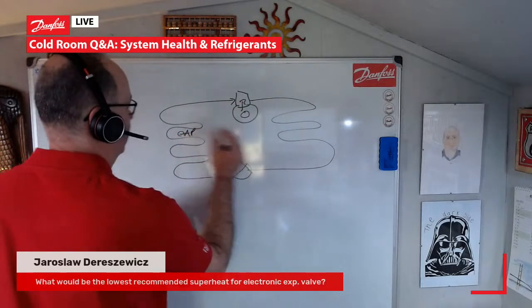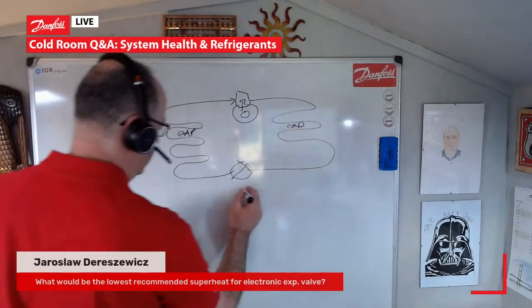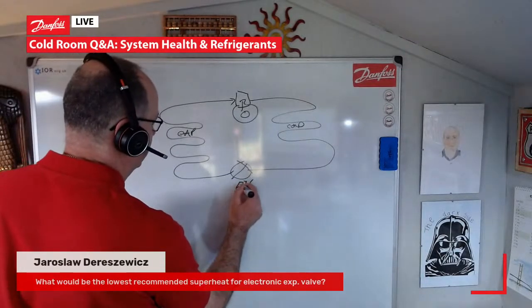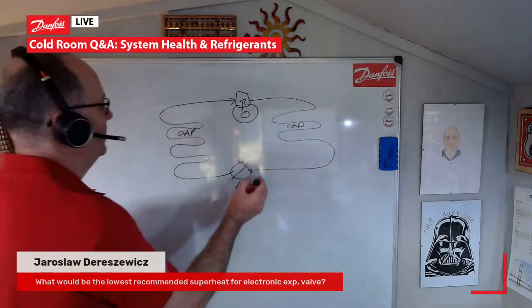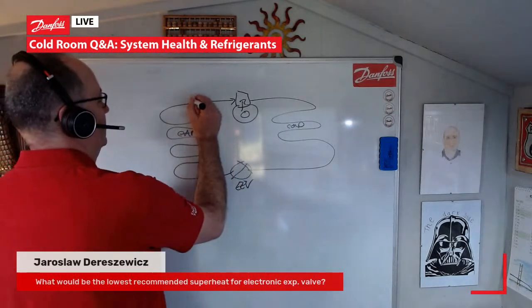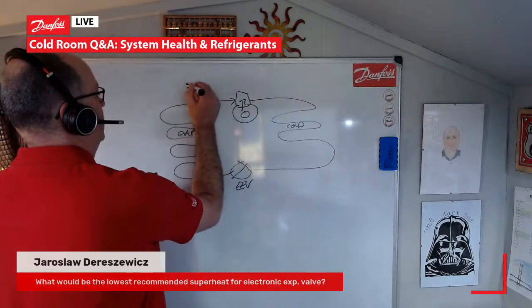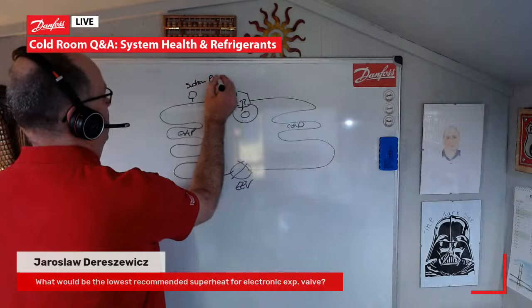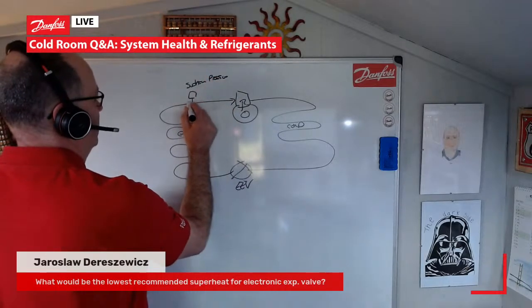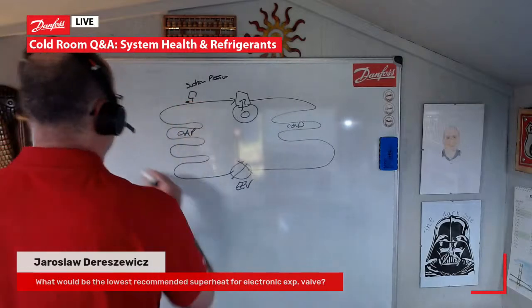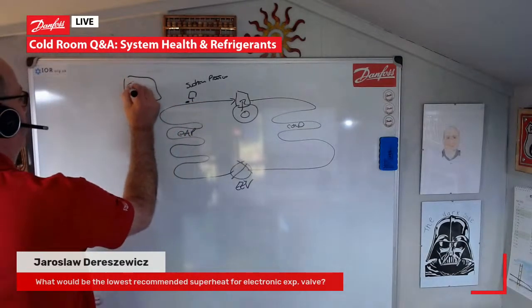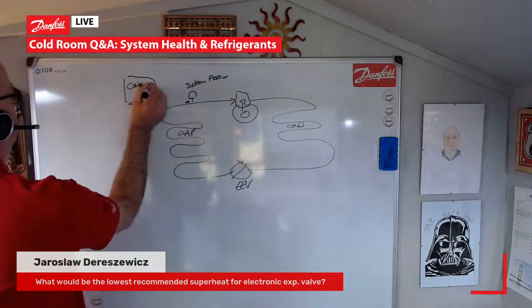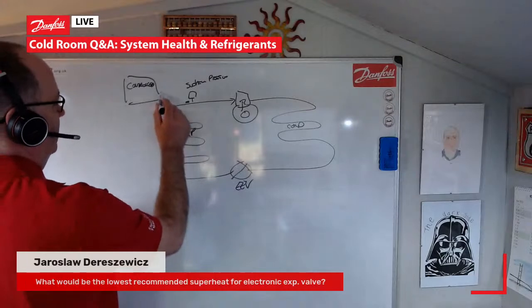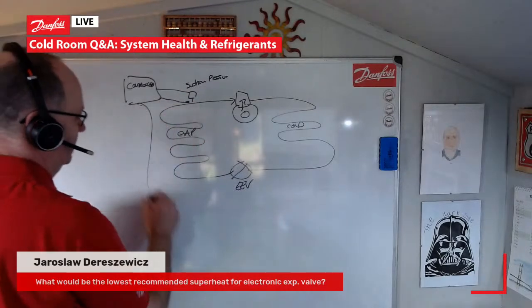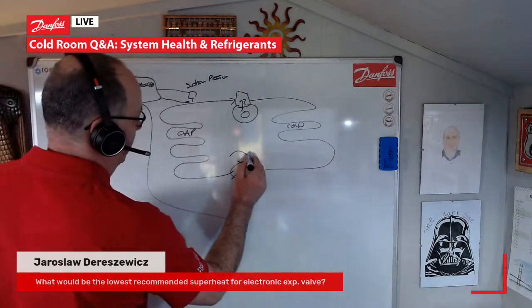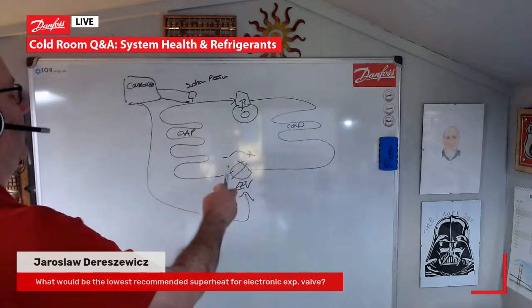So that's our evap, that's our condenser again. If you've got an electronic expansion device, an EEV, we control the EEV by a pressure transducer that measures suction pressure, and then we have a temperature sensor that is controlled by our controller, something like that, and that measures that, and then controls that in a positive or a negative. So we open and close it accordingly.